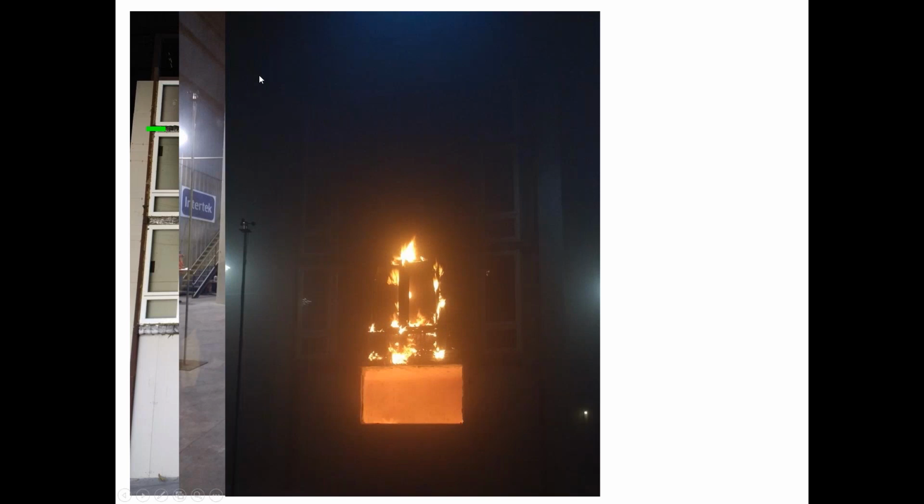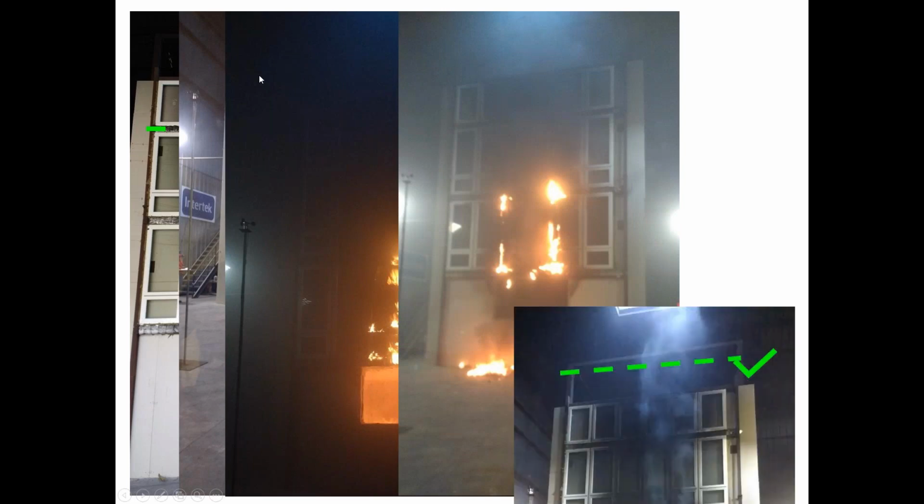So this was the maximum extent of burning at the end of the flaming period, the end of the first 25 minutes, which was great because after that point, the window frames started to put themselves out on their own, and by the end of the test, had put themselves out. So we were very happy about this. This is a fantastic demonstration of preserving fire safety.